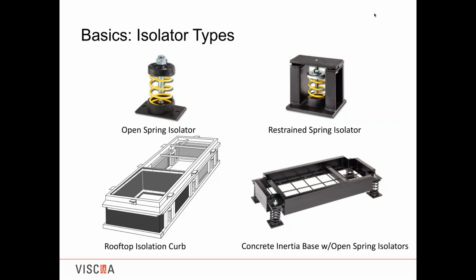So the installed height of the equipment is the same as the free height as it's vibrating. And the upper plate on that one moves independent of the lower housing. So the lower housing stays anchored to the building. The upper plate, which is attached to the equipment, will float and move up and down with the equipment.